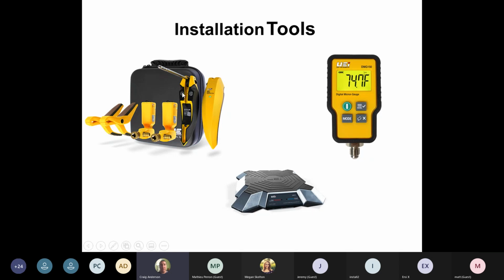You have 2 pocket thermometers that go in your supply and return. This attaches to your phone via Bluetooth. It's going to give you everything you need on that air conditioner. It's going to give you superheat, subcool. It's going to tell you your return air and supply air temperature. It's going to tell you the temperature of your liquid line and your suction line. It tells you everything. If you add a smidgen of gas, it's going to tell you on your phone what has changed.